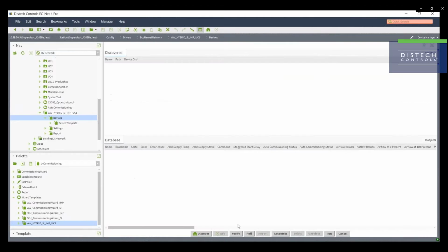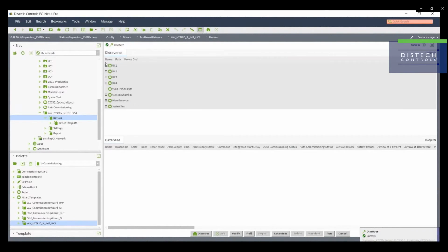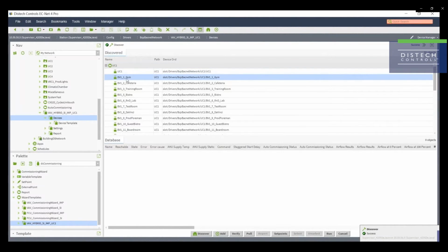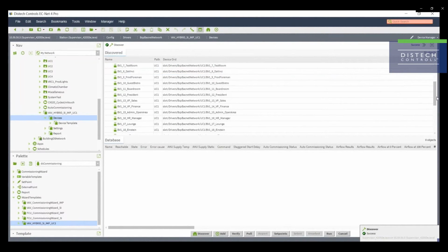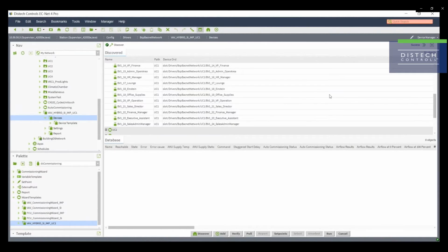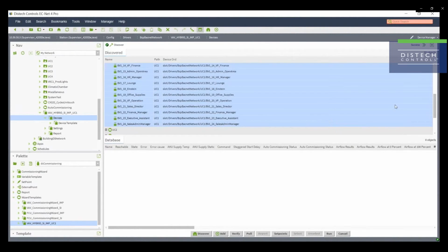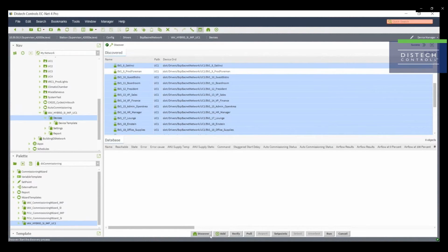Now let's navigate to the device manager of the commissioning wizard and we'll do a discovery. This will return all of the ECLYPSE devices in the BCP BACnet network. From here, we will select the devices we wish to test and we will add them to the database. You can see I unselected a device. I do not want to include this device in my test.